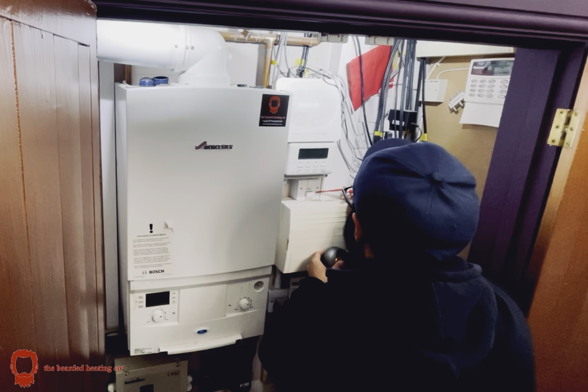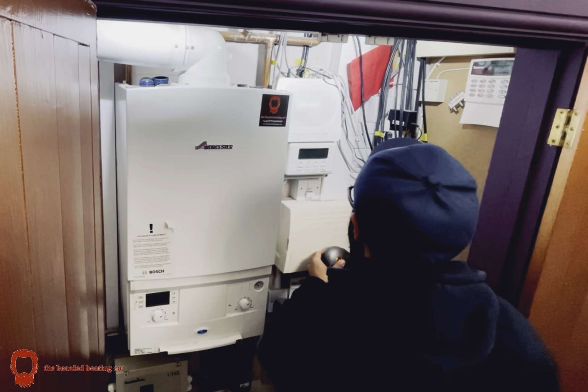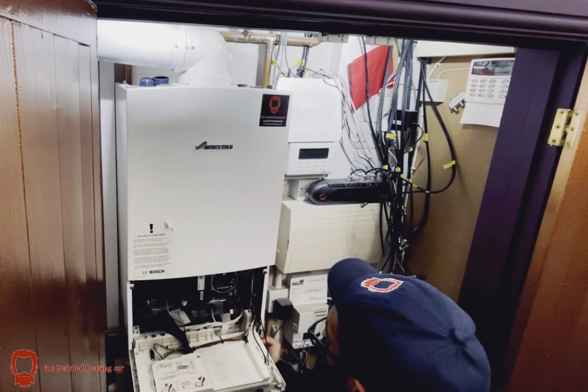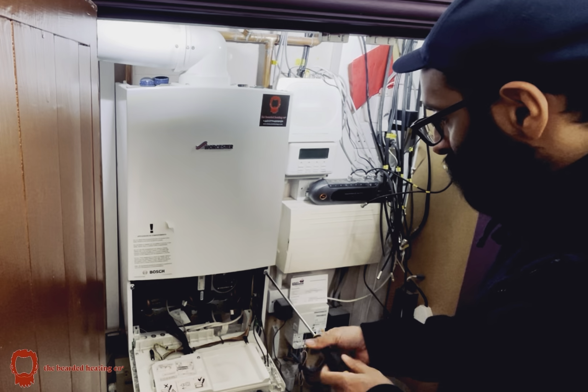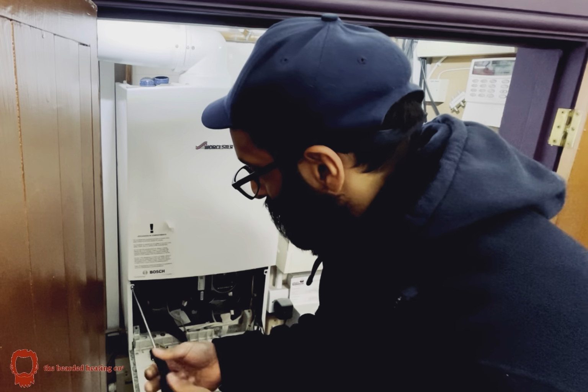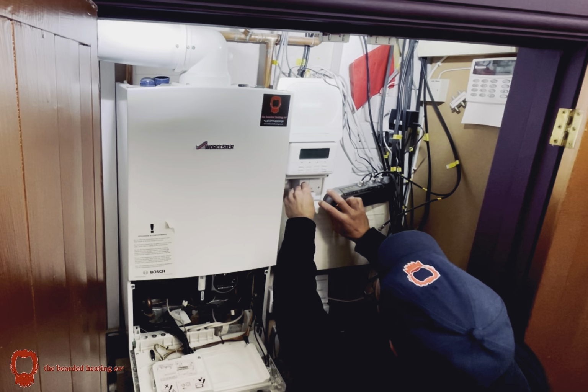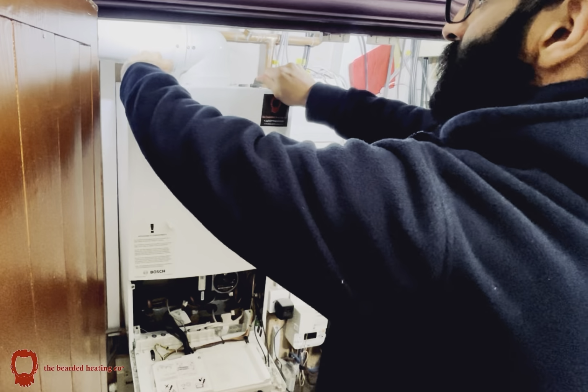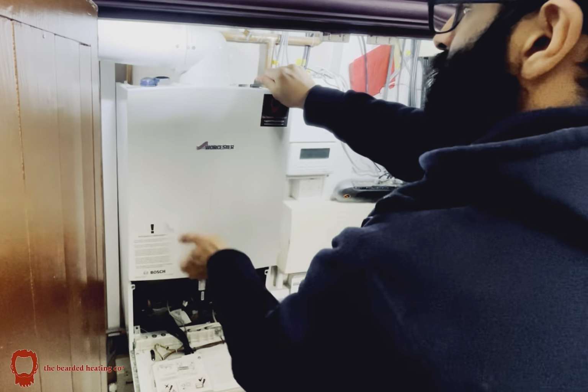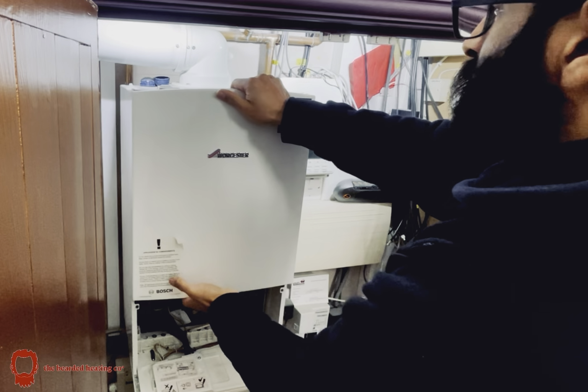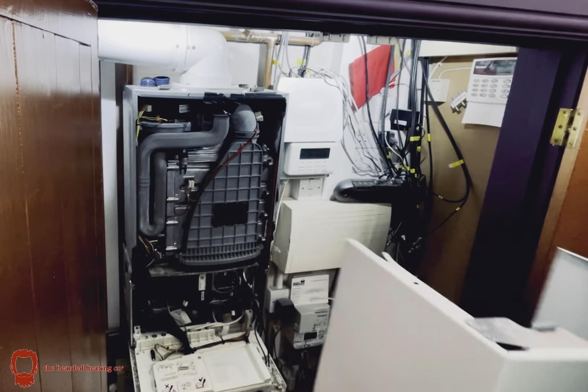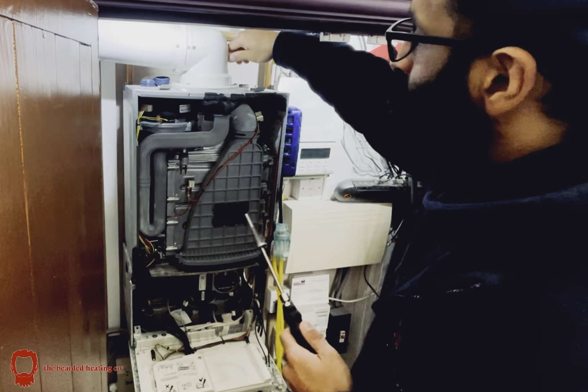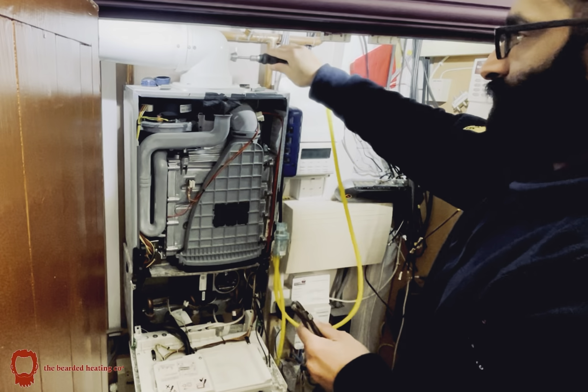In this one I am stripping down a Worcester 27i system boiler because the negative fan pressure was so low that my CO on low fire was above 200 parts per million, and it should be less than 50 parts per million. So therefore I carried out a strip service on this boiler.